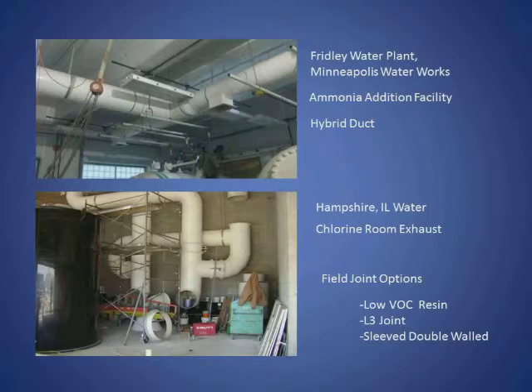Next, we're looking at the Fridley water plant in Minneapolis, ammonia addition facility. Water plants add chlorine to the water as it leaves the plant and goes out to your homes and business. And what they call residual chlorine is what you end up with in your tap at home. And it's always been very difficult to control. And it's very important because that's what keeps our water clean and safe. It was discovered maybe 10 years ago that the addition of small amounts of ammonia can control that residual chlorine.